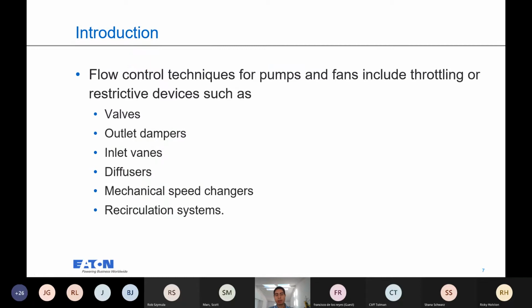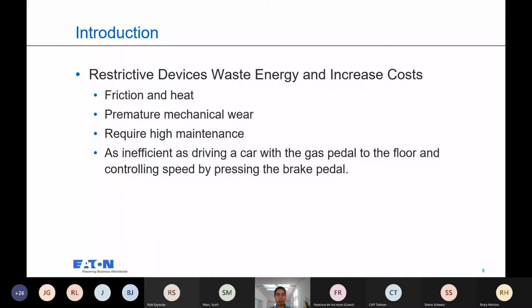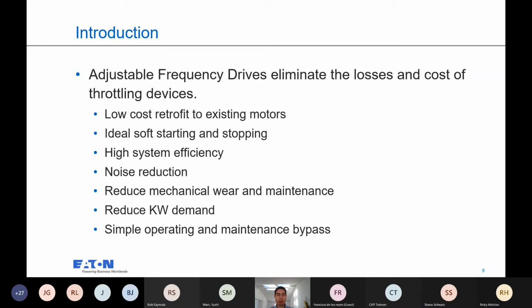So let's start on flow control. How do you achieve flow control traditionally? Valves, dampers, vanes, diffusers. We'll go through how that affects the system head pressure and efficiency of your system. Recirculating systems are another way of achieving this. All these restricted flows and devices increase the heat and the friction, create wear on your equipment, and require maintenance. A great analogy is pushing the accelerator pedal and then controlling the speed of your car by just hitting the brakes. So obviously we want to avoid that.